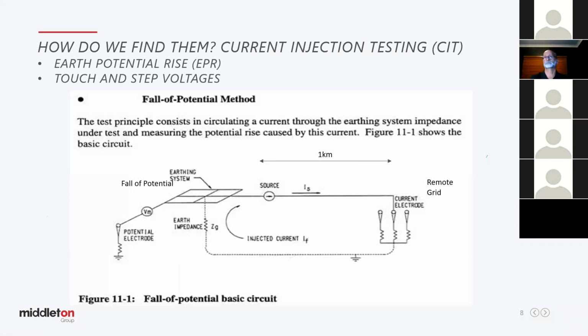So how do we find them? Well, one method we commonly use is the current injection test. Using this test, we can measure the earth potential rise that we've been discussing. And we can also measure touch and step voltages and compare them to the standards. So on your screen there, you can see the method, current injection test, commonly called the fall of potential method.